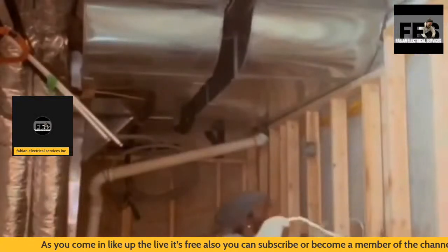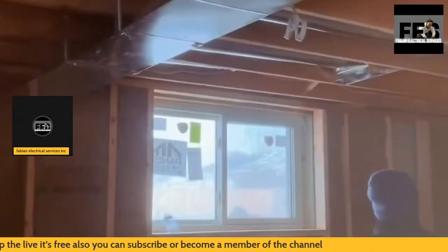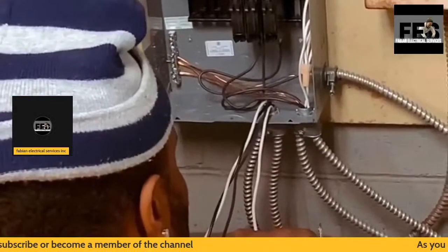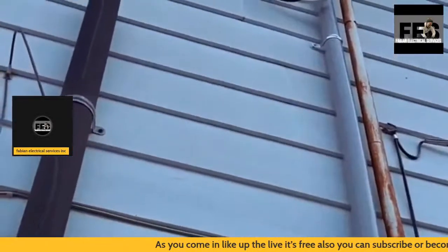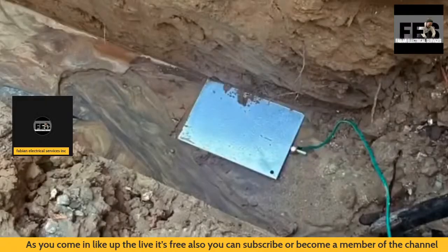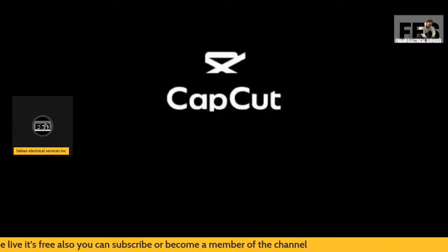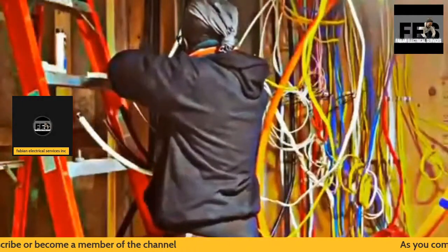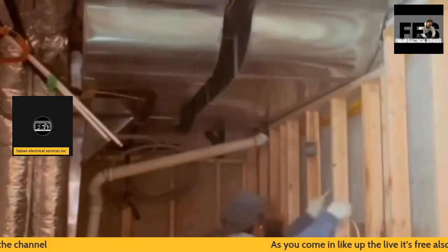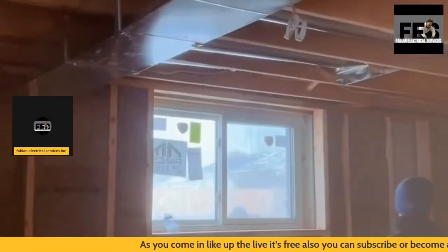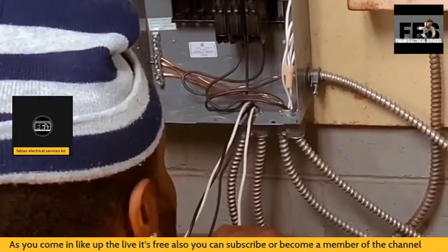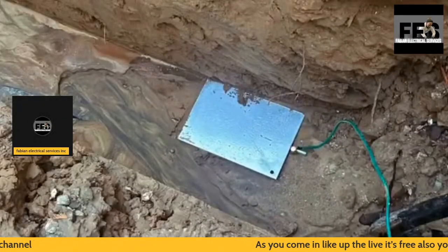Also, you would have seen in the video me phasing my electrical wires. This set of cable doesn't come with a neutral, what we call an unidentified conductor that needs to be identified. So the code rule, staying within code compliance, states that electrical tape can be used to identify your cables. That's basically what I'm doing. Obviously it has to be white, that's what we need to identify. So it's white.